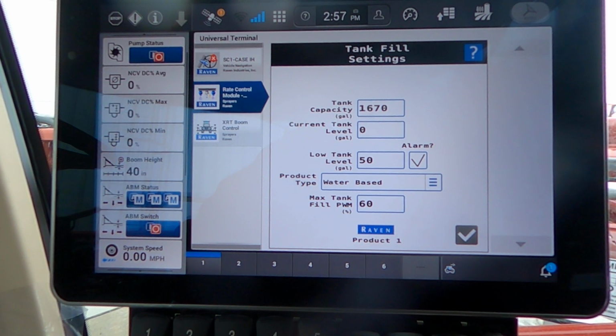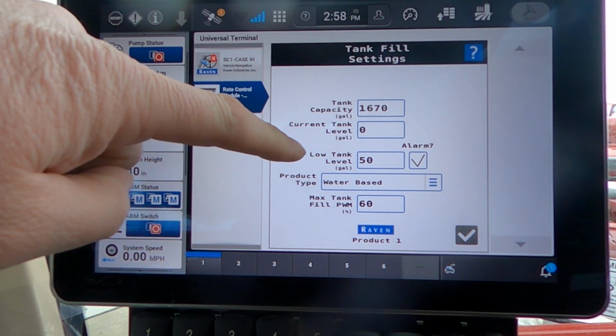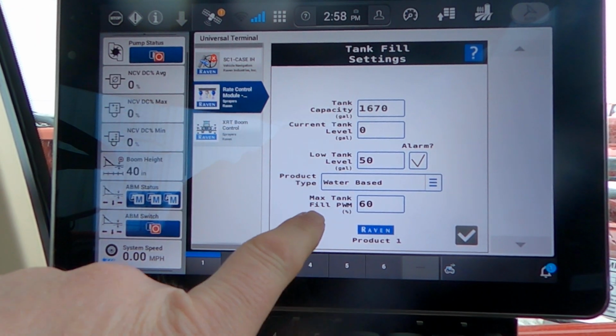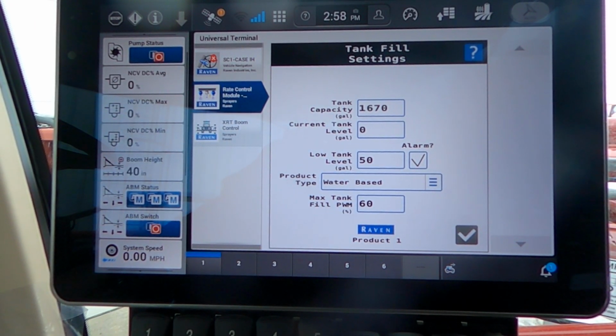Okay, current tank level. Right now our tank is empty, so 0 gallons is correct. If we accidentally hit the flush button and it removed the gallons, we could then manually enter something, but normally the flow meter will calculate that as we fill the machine. Low tank level alarm, 50 gallons, 100 gallons, 150, whatever you prefer. You can change that setting here. Max tank fill PWM 60%. That is what the pump will run at when you turn the manual pump switch on out at the fill station. That'll run the pump at 60% for mixing or filling.